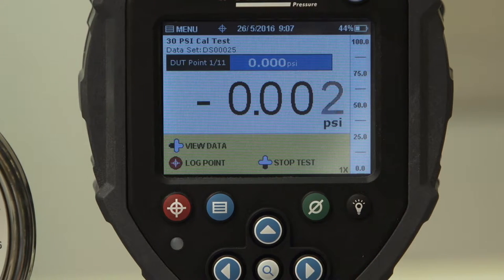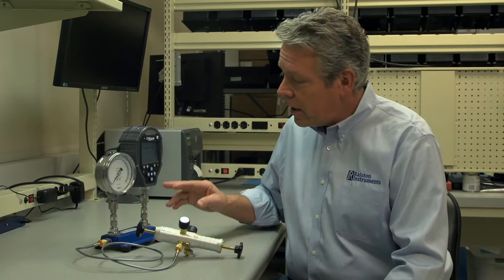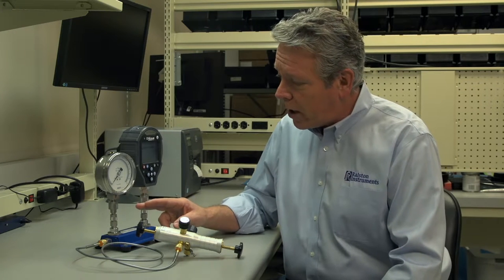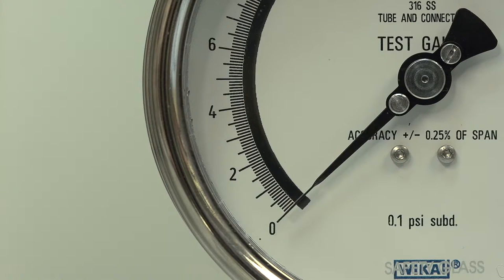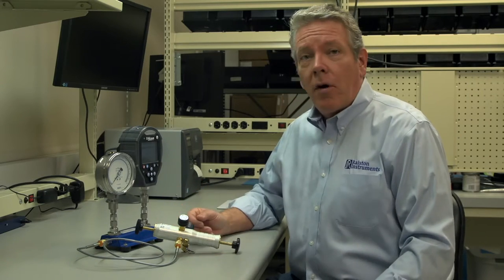I'm prompted on screen for the first test point, in this case zero psi. As we can see our first test point is zero and with no pressure applied our needle is right on the zero hash mark. Since no pressure has been applied yet the Field Lab also reads zero.